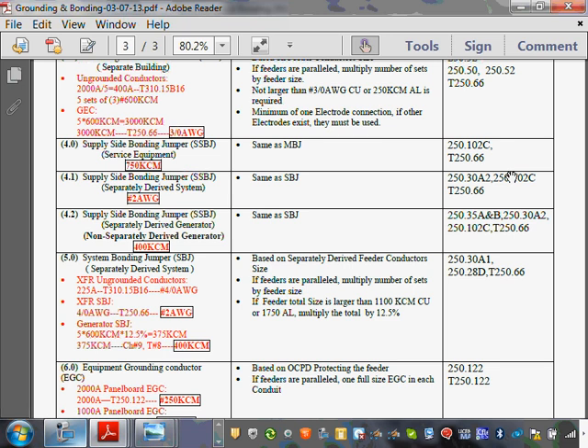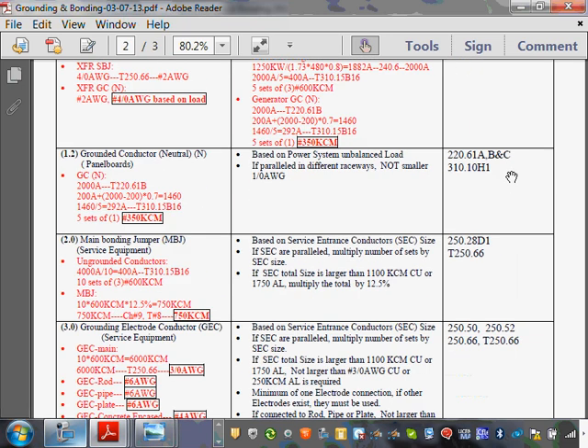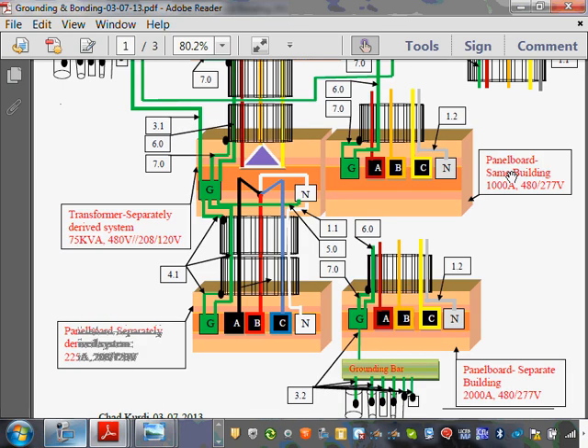The only difference between them is the name and where they're located in the system. So that's my system bonding jumper, and its size is number 2. Any comments, guys? Any questions about the system bonding jumper? So we went to my system bonding jumper. That's the first thing you do: you have to ground your neutral.